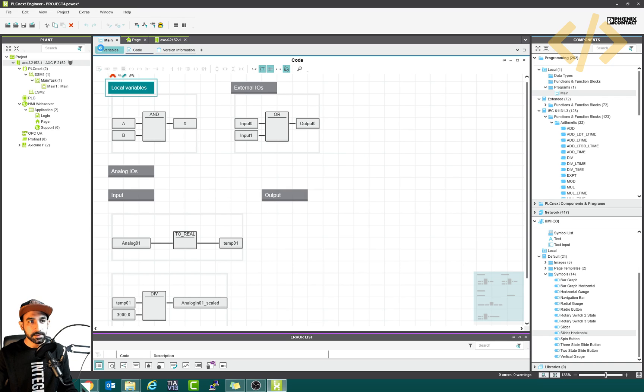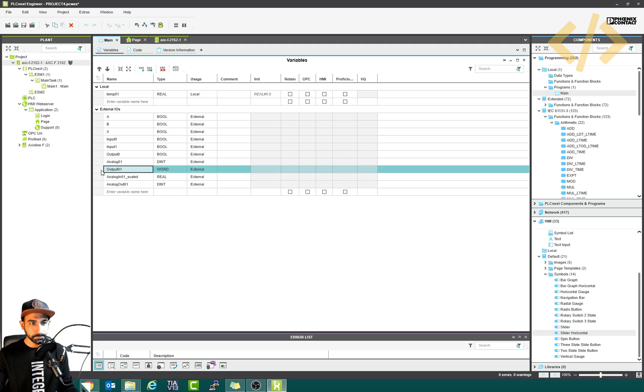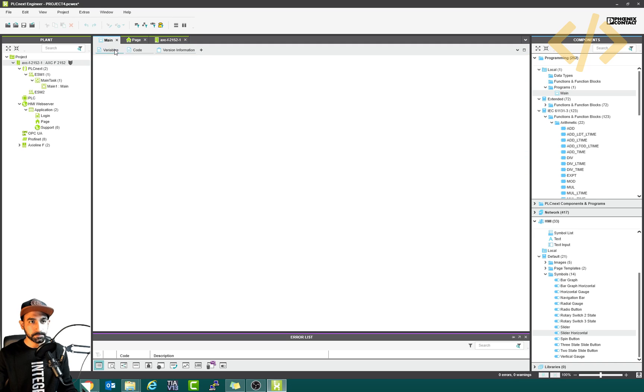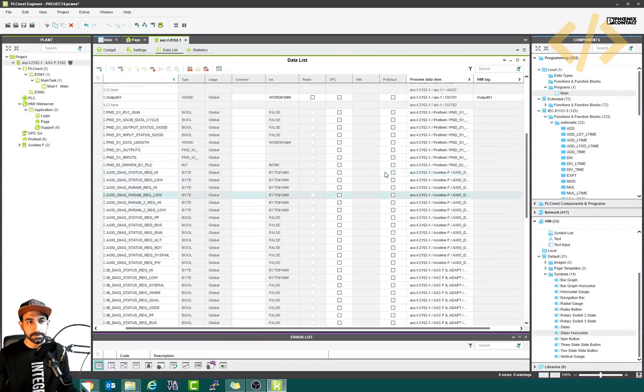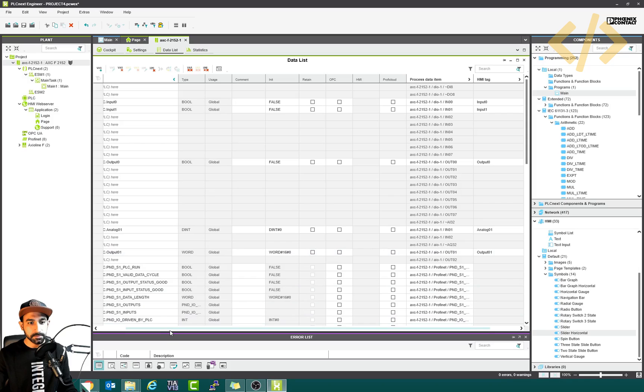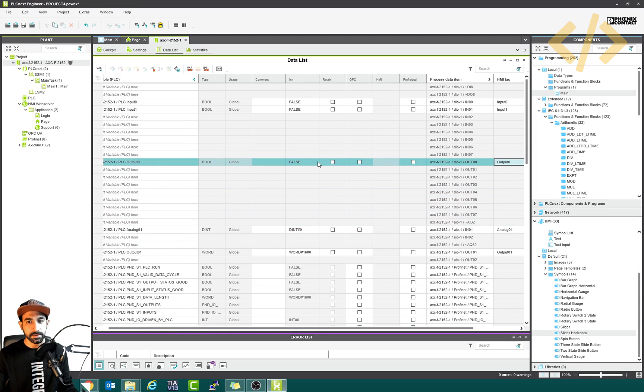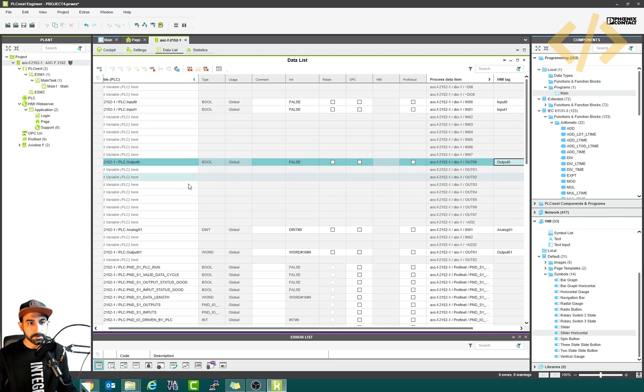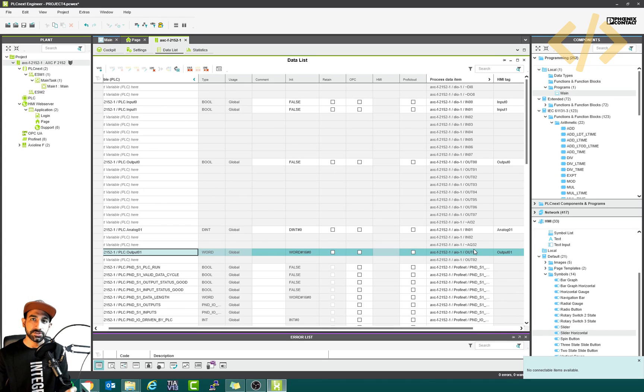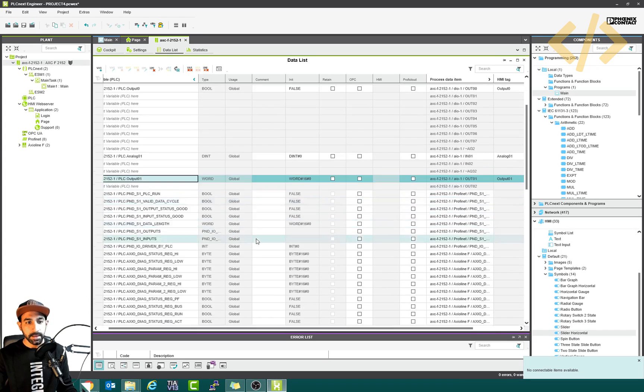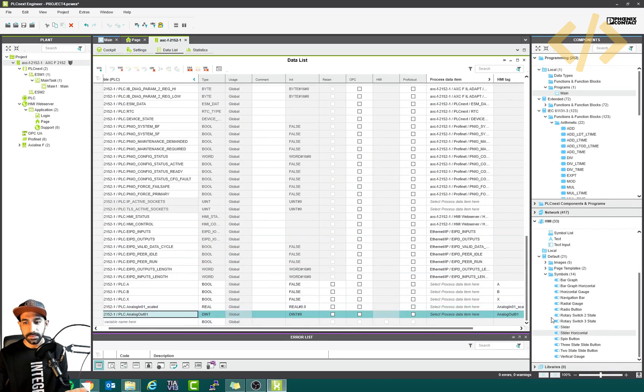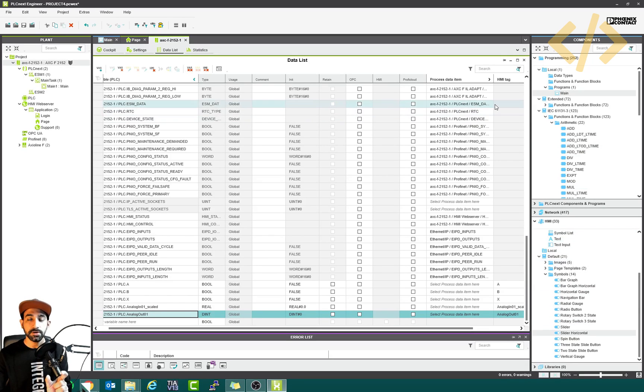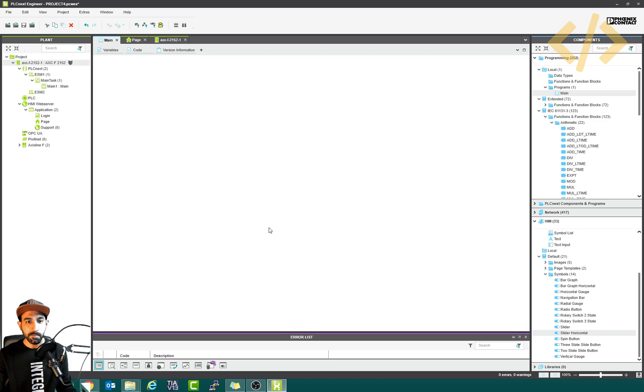And wait a second, I need to check something. We already have this tag analog 01 which is linked. If you remember, this tag is linked to your I/Os, analog I/Os. So this output 01, this tag is linked to your physical analog output out 01. This is where the voltage is going to be generated using this tag. And from the HMI, the values from zero to 30,000 are coming here. This is the HMI tag. So we have to move the value from here to your physical I/O tag. But this is in digital int, we need to convert that to word. That's what we're going to do now.